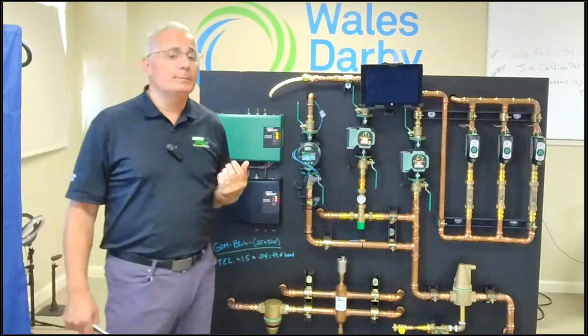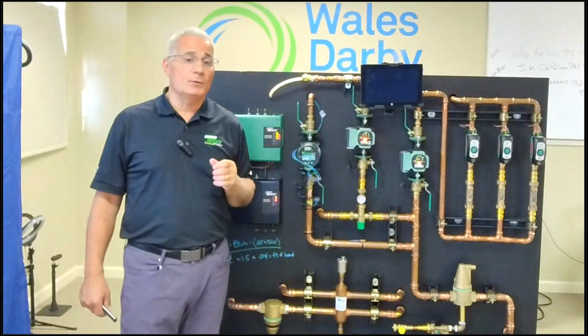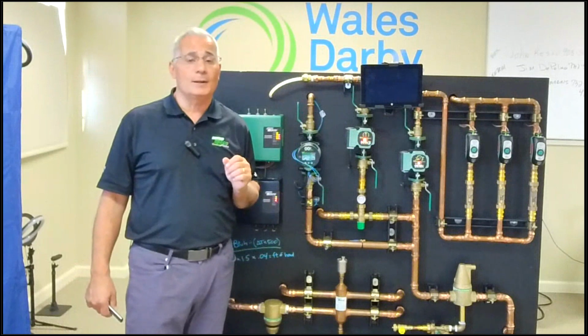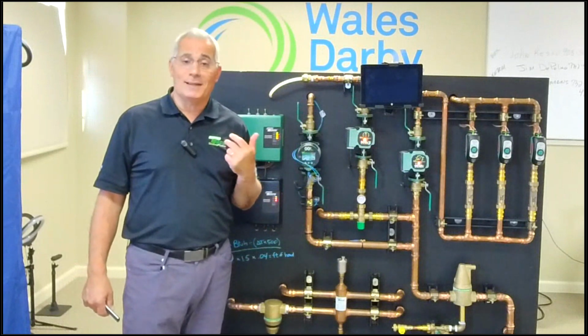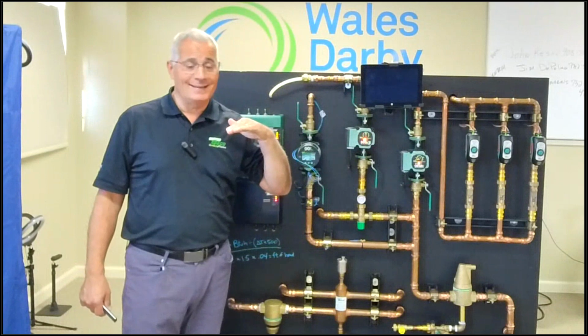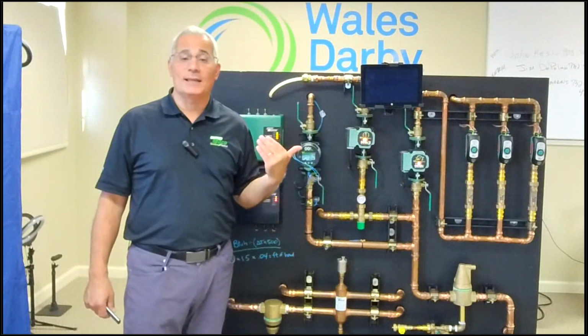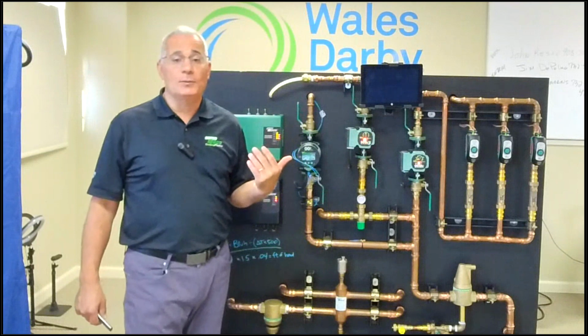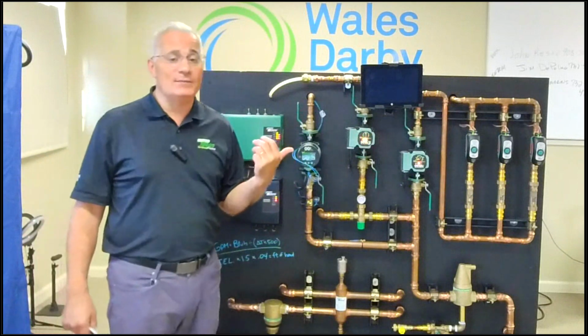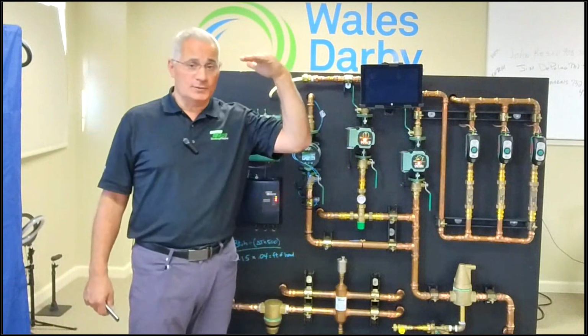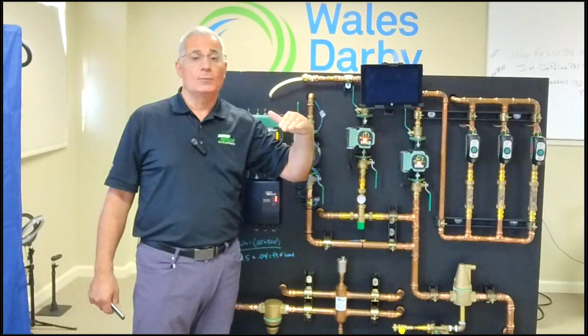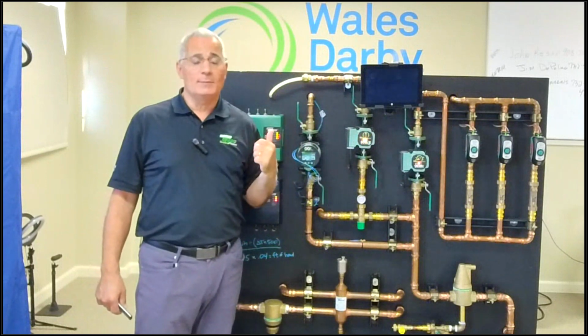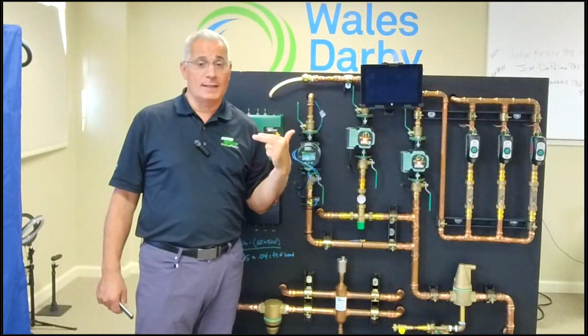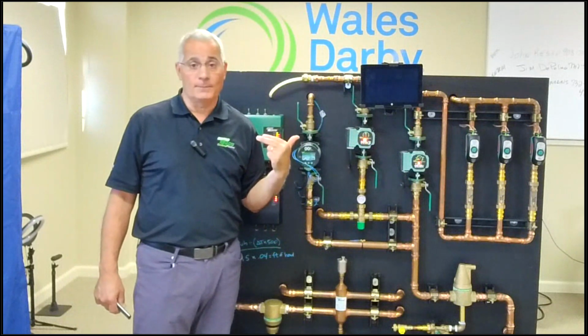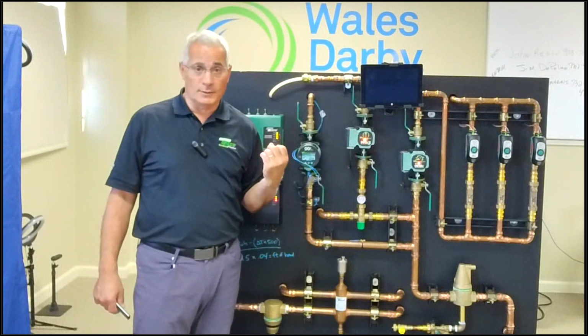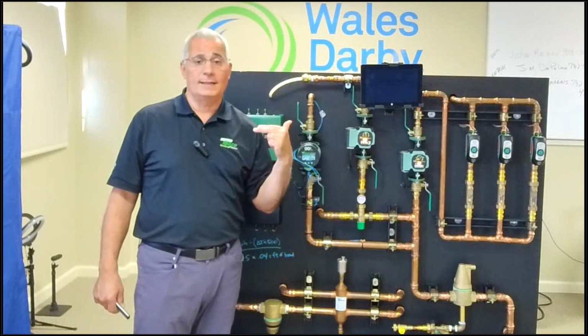You have learned from our previous webinars that we want to make sure that when we size our boilers, we are doing a proper heat loss, because what we're concerned about is making sure that at its lowest end, I'm still not dramatically oversized for that smallest zone. So a lot of these boilers have 5-to-1, 10-to-1, 11-to-1 turn downs. Those are steps in the amount of BTUs where it can fire. So I do want to be aware of getting my low end as tight to my system demand as possible. So even if my smallest zone calls, I want to make that low end as tight to that BTU demand as possible.